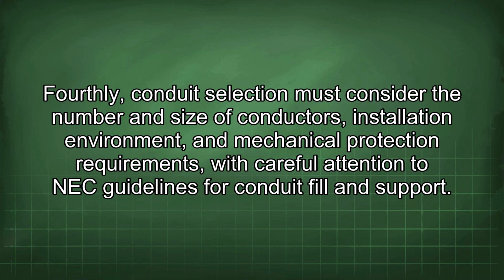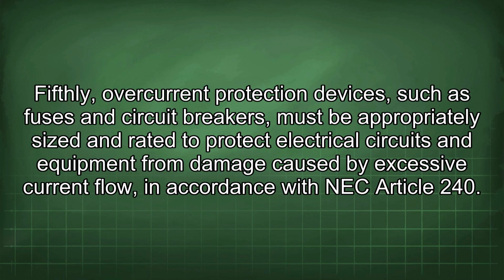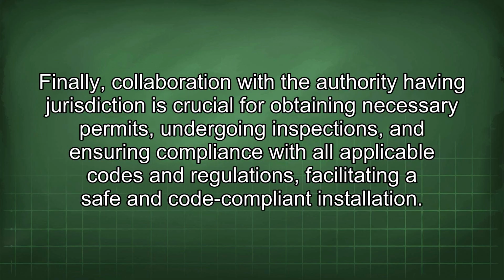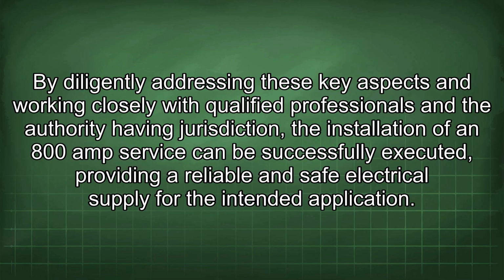Fourthly, conduit selection must consider the number and size of conductors, installation environment, and mechanical protection requirements, with careful attention to NEC guidelines for conduit fill and support. Fifthly, overcurrent protection devices, such as fuses and circuit breakers, must be appropriately sized and rated to protect electrical circuits and equipment from damage caused by excessive current flow, in accordance with NEC Article 240. Finally, collaboration with the authority having jurisdiction is crucial for obtaining necessary permits, undergoing inspections, and ensuring compliance with all applicable codes and regulations, facilitating a safe and code-compliant installation. By diligently addressing these key aspects and working closely with qualified professionals and the authority having jurisdiction, the installation of an 800 amp service can be successfully executed, providing a reliable and safe electrical supply for the intended application.